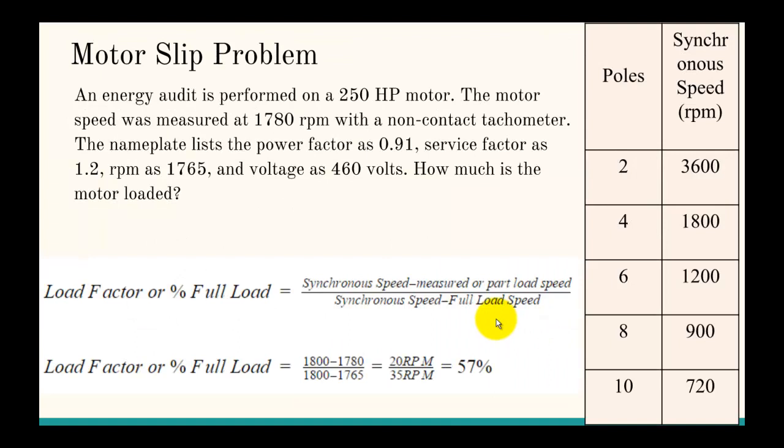Motor slip. Motor slip is a way to basically measure how much a motor is loaded, and usually you are using a tachometer which is measuring RPM. In this case an energy audit is performed on a 250 horsepower motor. The motor speed was measured at 1780 RPM with a non-contact tachometer. The nameplate lists the power factor as 0.91, service factor as 1.2, RPM as 1765, and voltage as 460 volts. How much is the motor loaded? It turns out there's actually a good bit of extra information here. You don't need the 250 horsepower, the power factor, the service factor, or the voltage. All you need is the RPM values here, the 1780 RPM and the 1765.